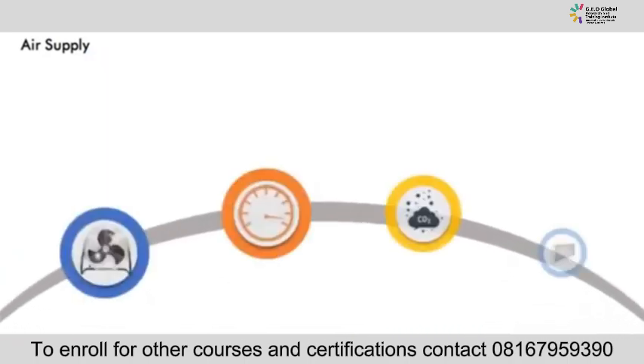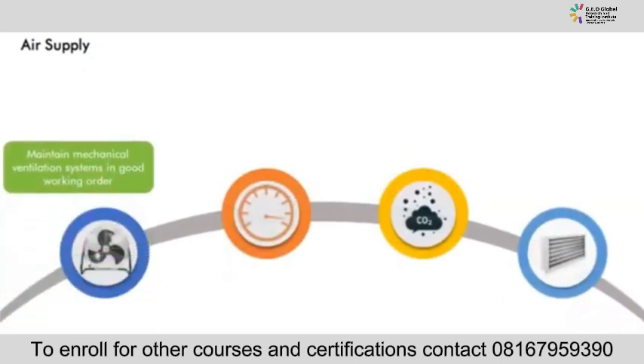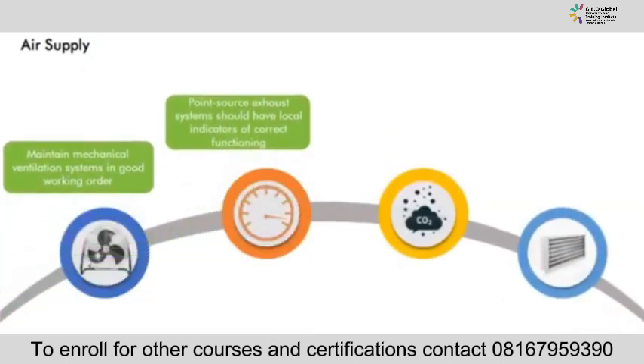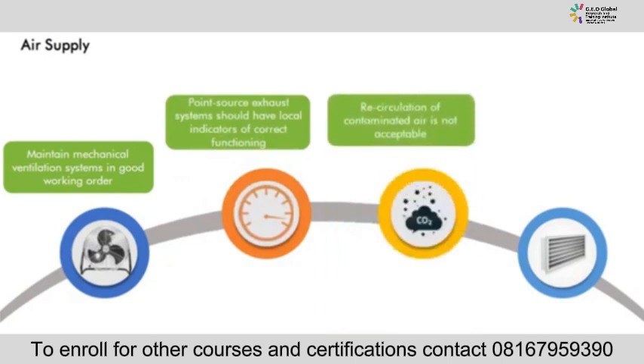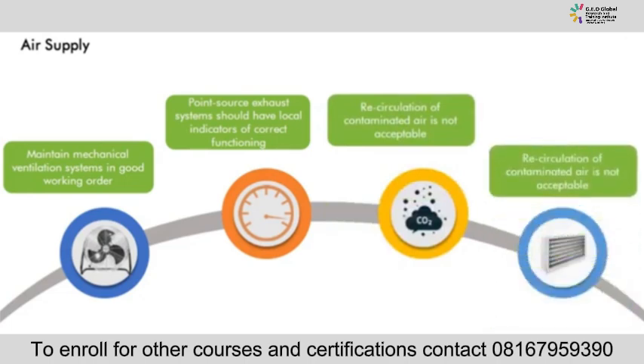Mechanical ventilation systems should be maintained in good working order. Point source exhaust systems required for maintaining a safe ambient environment should have local indicators of correct functioning. The recirculation of contaminated air should not be acceptable. Air inlet filters should be kept clean and free of dust and microorganisms.